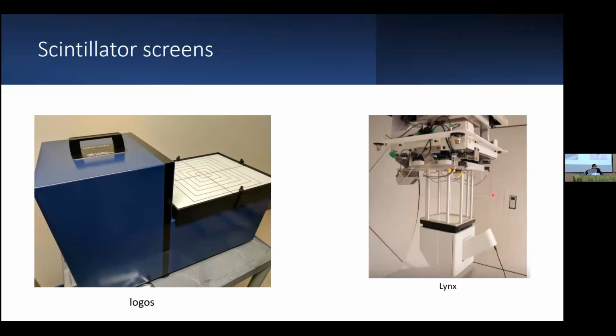Here's a different one. This is a Logos system, and this right here is called the Lynx. These are just names that different vendors give their equipment. These are all scintillator devices. The way scintillators work is you hit them with the radiation, and they light up. You have a camera that looks at it. The vendor that you get this equipment from should be able to give you the specifications, but you have to make sure that it's not being skewed. Anytime you have a camera looking with a mirror bending the light so you can look at it, you're going to get some distortion. Usually the vendor would already try to correct this distortion, but maybe not.